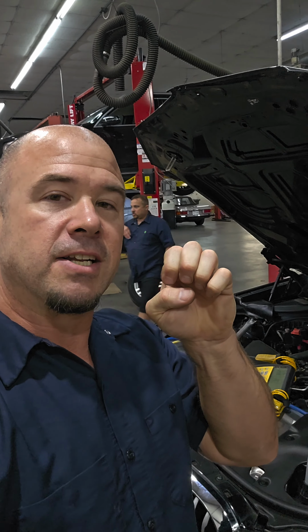So what does that tell us? Well, we know that the front seal of the air compressor, the seal that goes around the shaft, is being pulled or deformed under heavy vacuum, which is causing a leak.